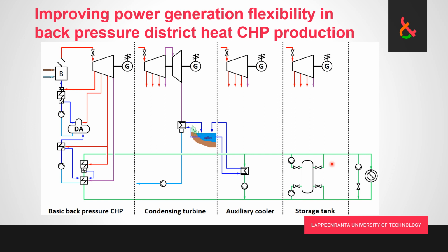and then when the opposite is true and we have the situation that we have very low electricity cost, then we can, instead of wasting fuel to produce electricity and heat, well, heat is always usually the same price, but to produce electricity when we get relatively little profit from it, then we are unloading this tank.